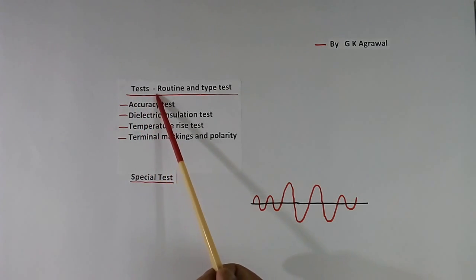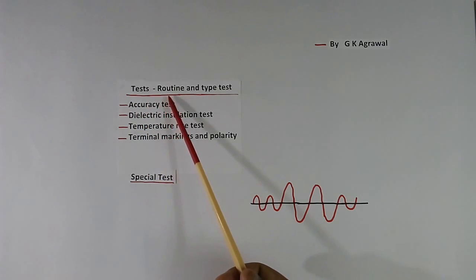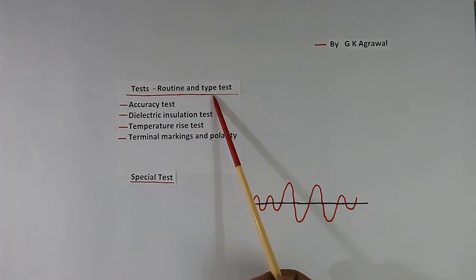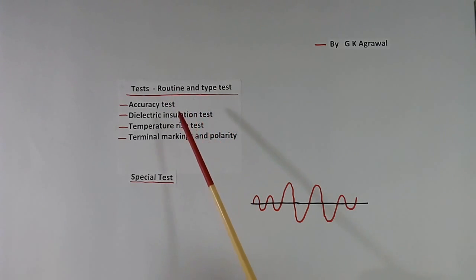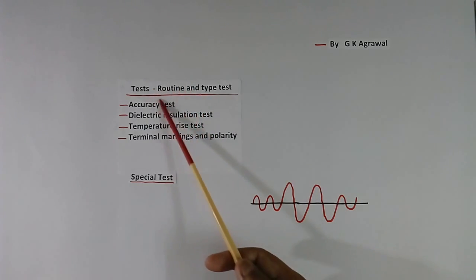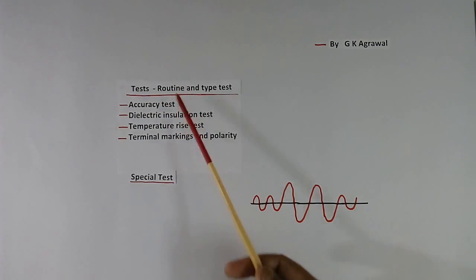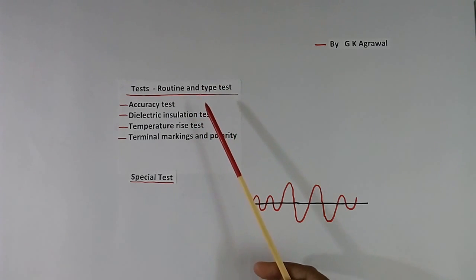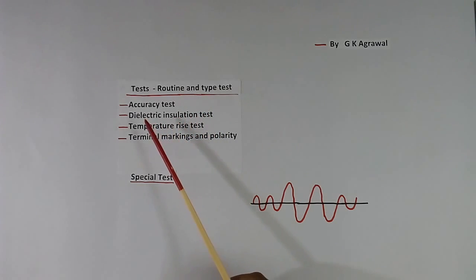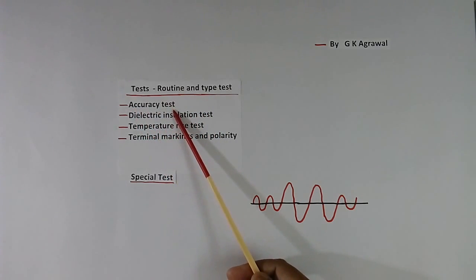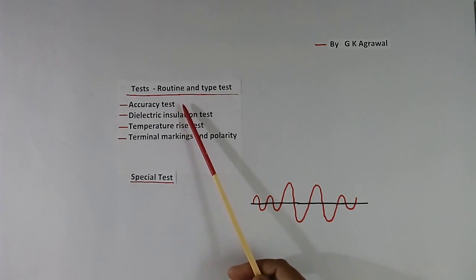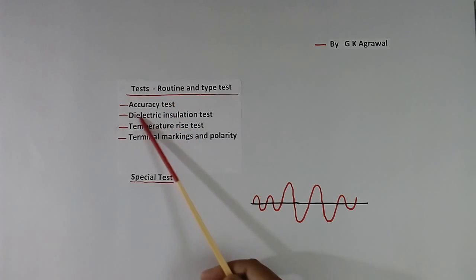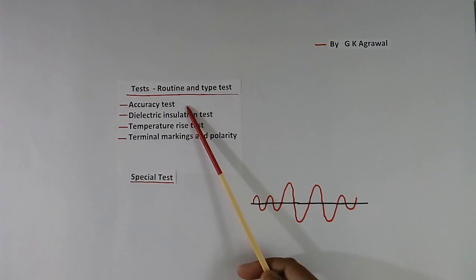Now we come to tests. Tests are of two types — routine and type tests. Suppose we want 10 transformers: routine tests will be done on all 10, but type tests will be done on only 1 or 2 transformers. Then there is the accuracy test — we check whether the output voltage is coming accurately or not. Before doing this test, we check that the multimeter is accurate and properly calibrated.